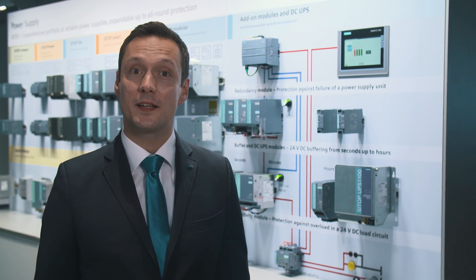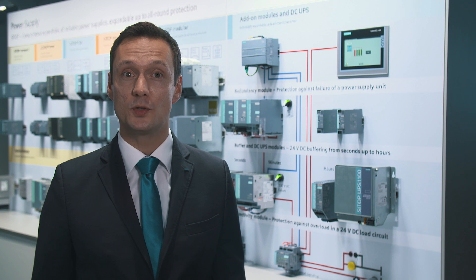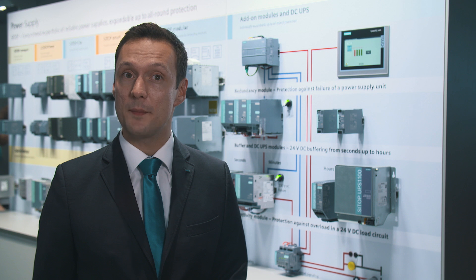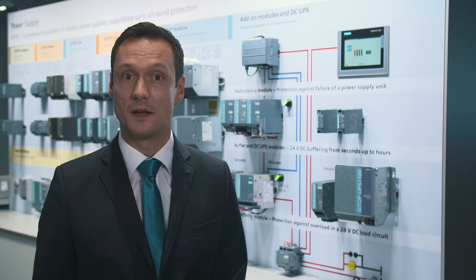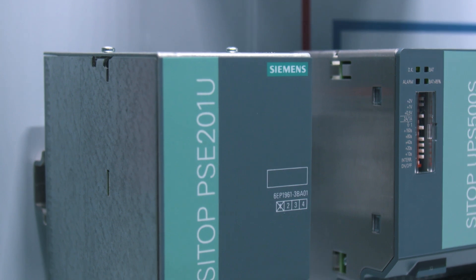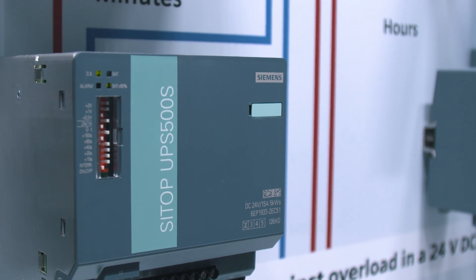The SITOP DC UPS modules ensure smooth plant operation during various power failures and help to save time and money. The buffer module ensures reliable 24-volt supply for up to 10 seconds, and the maintenance-free DC UPS with capacitor technology provides even minutes of backup.